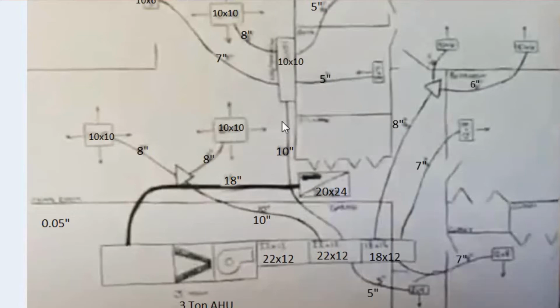Now, we go back to our air handler unit. Let's just say we go in the manufacturer's log or data book, we figure out that our air handler has a pressure rating of 0.5 inches. That's a good average for an air handler. Then we start taking off any pressure drops for anything in our airstream. So where are we going to hit a pressure drop first? Well, you would probably hit one on a resistive coil if it was a heat pump with electric backup. We don't have that here, so I'm not even including that.